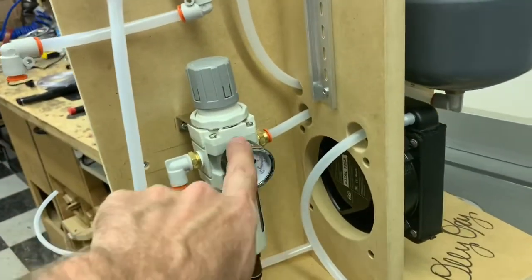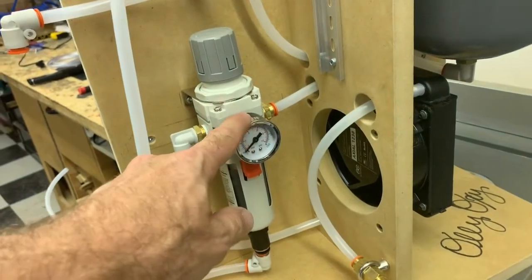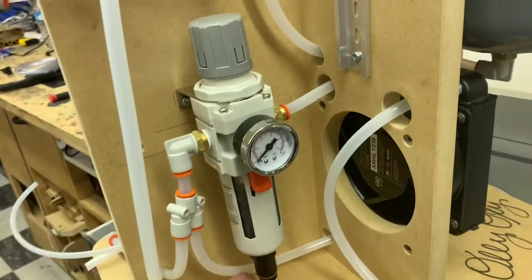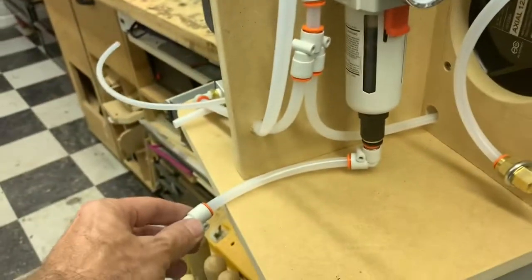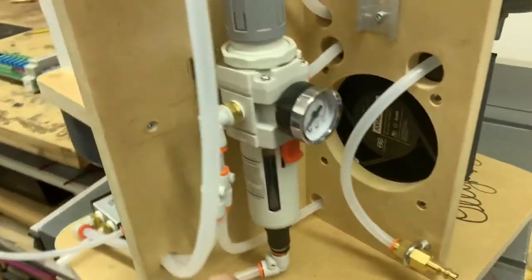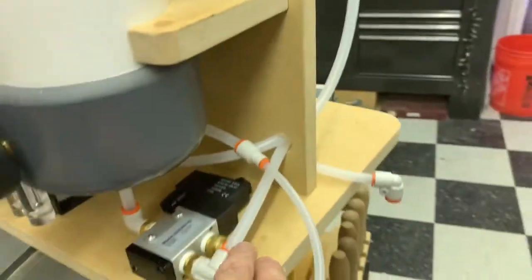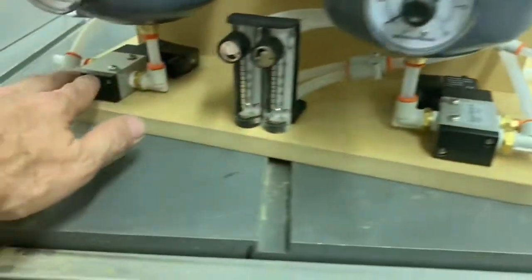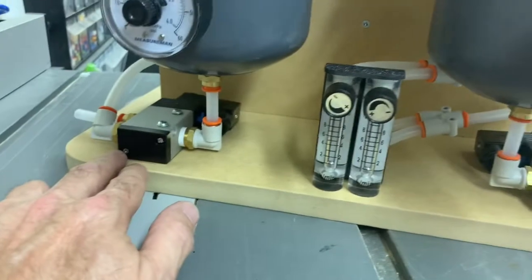Then we exit the radiator into a regulator. The regulator is a particulate filter as well as a moisture filter with automatic purging. So it'll purge any moisture that gets into the system out here automatically. Then these lines run out to the two feed valves, the right and left sieves, or sieve A and sieve B as we call them.